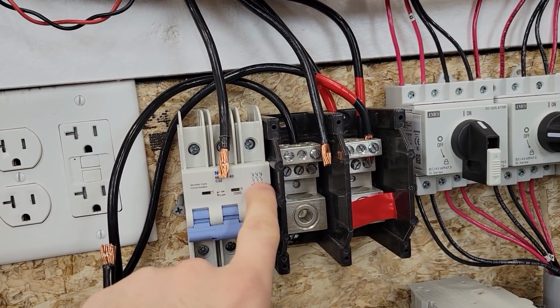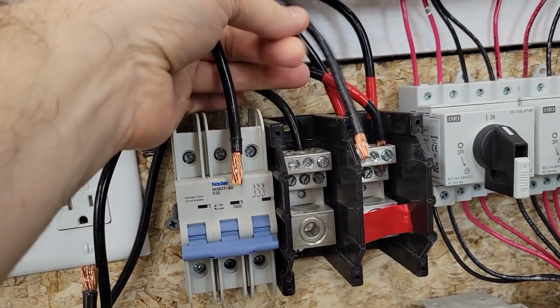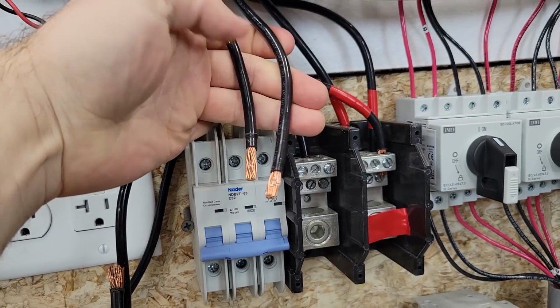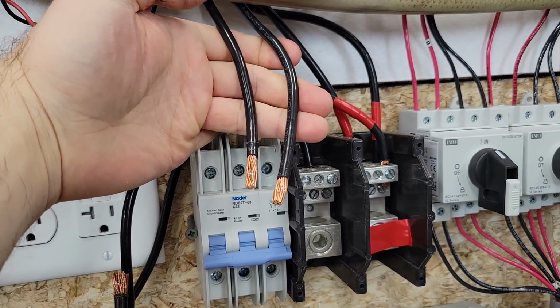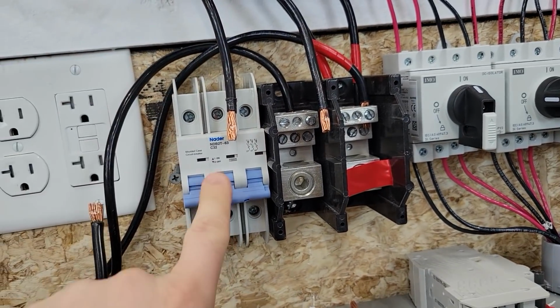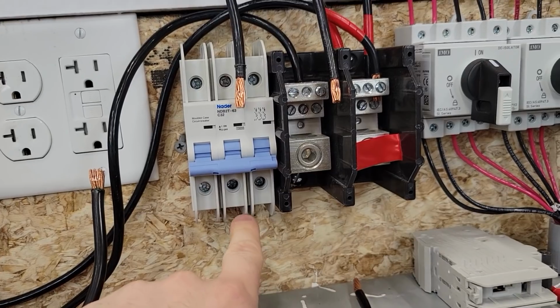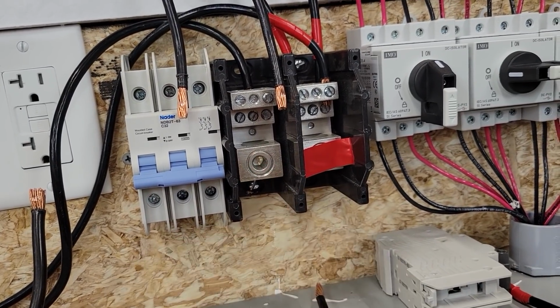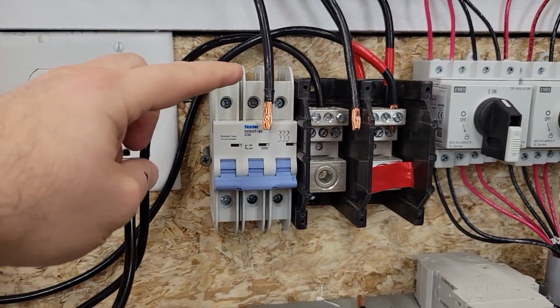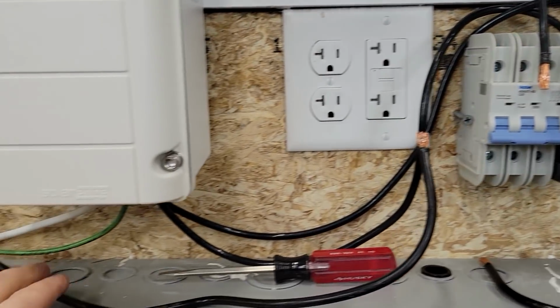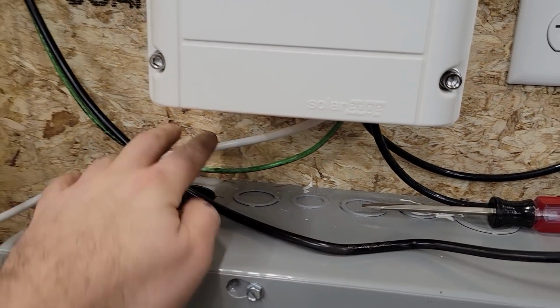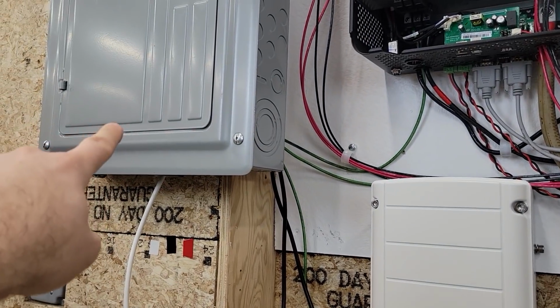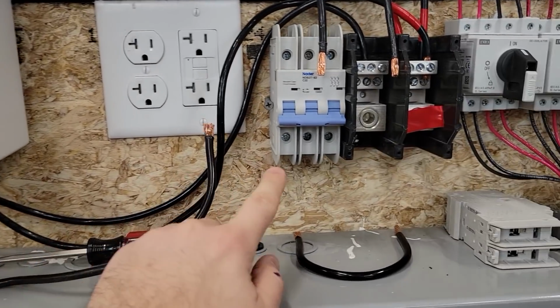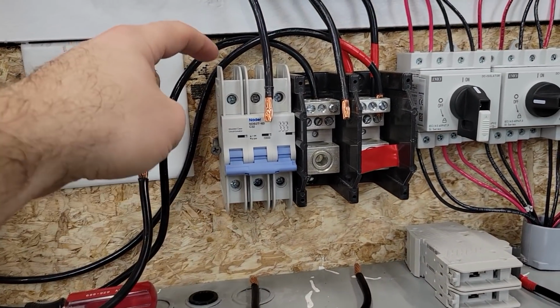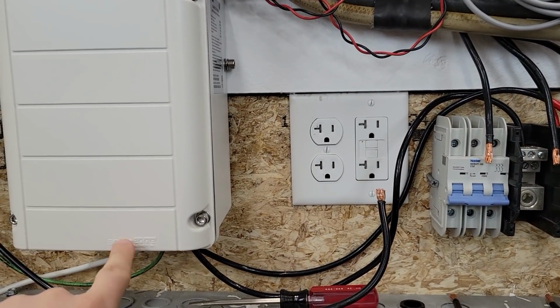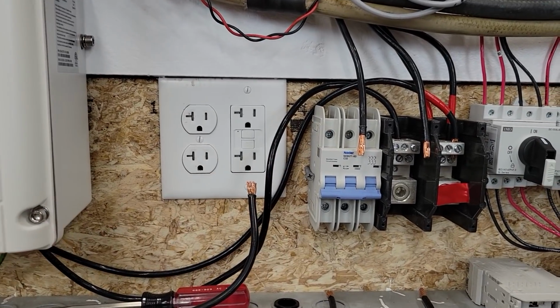So this is feeding the same phase, same L1, L1. These two wires are coming from inverter 1 and inverter 2. They're going to come in the top of this breaker. Out the bottom, we're just going to jump to this pole. The last one here is going to be for the neutral. So I need to move this neutral wire, which goes from the auto transformer into that box. I'm going to move it to the output side of the breaker. And the input side of the breaker, we're going to run a brand new wire from the auto transformer to the breaker.